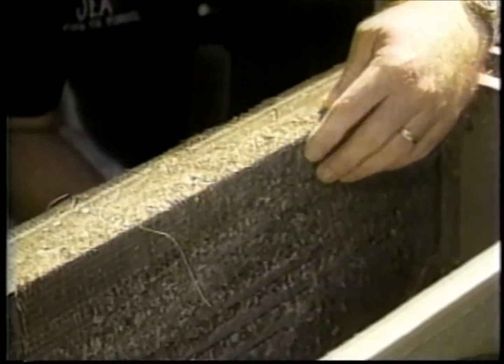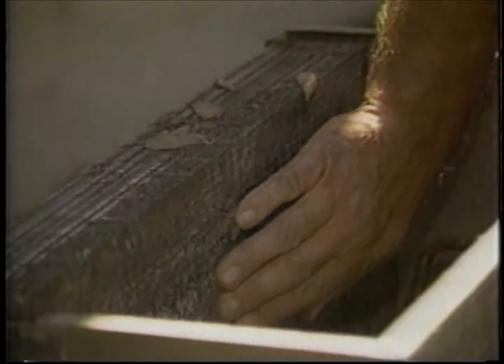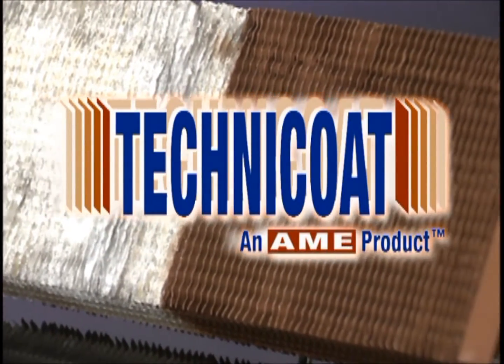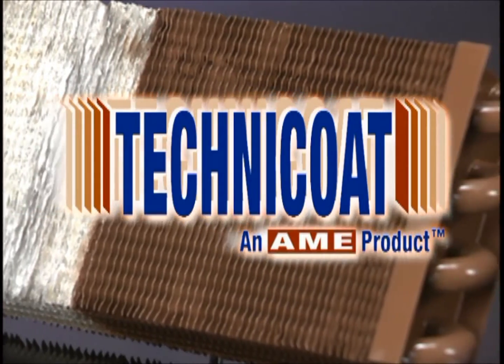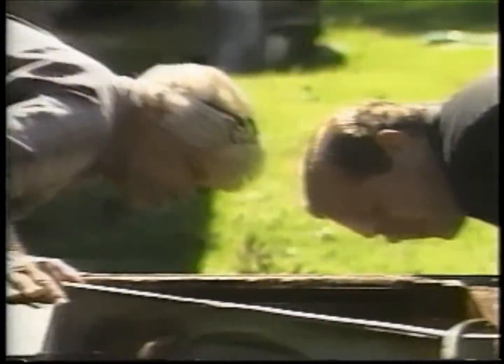The enemy was salt air atmosphere. After years of replacing air conditioning coils every 10 to 18 months on this tiny Pacific Island outpost, the Navy decided to try coils coated with Technicoat. 1,100 coils were installed at the Guam Naval Air Station base housing. Those coils were replaced over 12 years later.